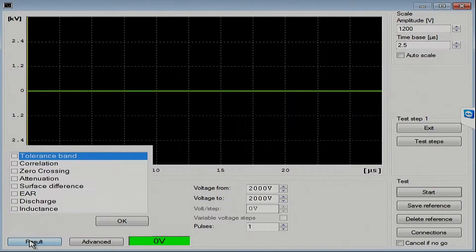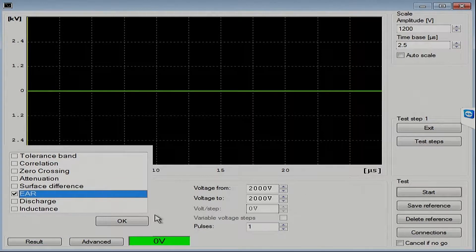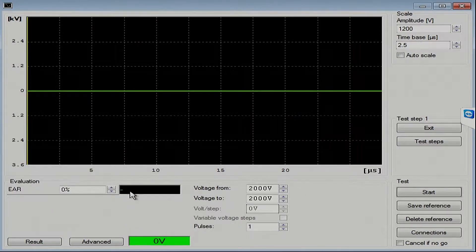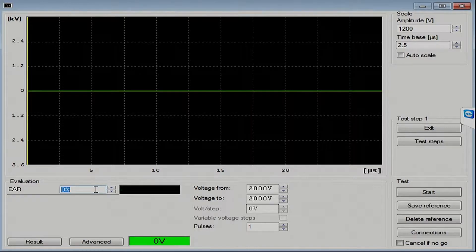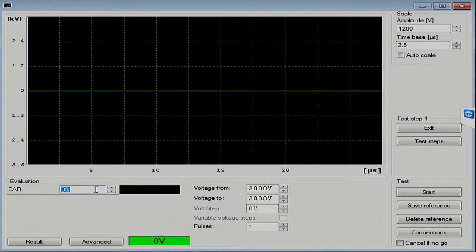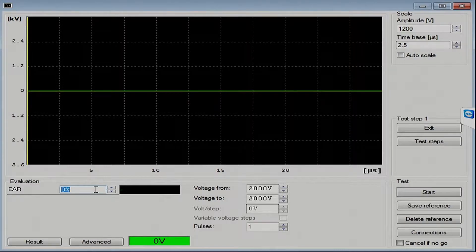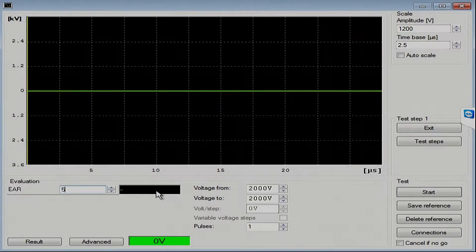There we've given our test voltage. I'm going to use an EAR as a way to measure the difference between those waveforms. And since this is a stator, I would expect a stator to have very similar waveforms. So, I'm going to give it 5%, see how that works.